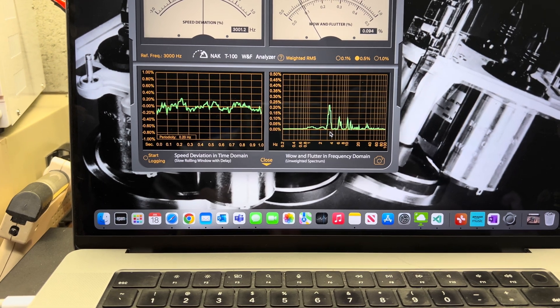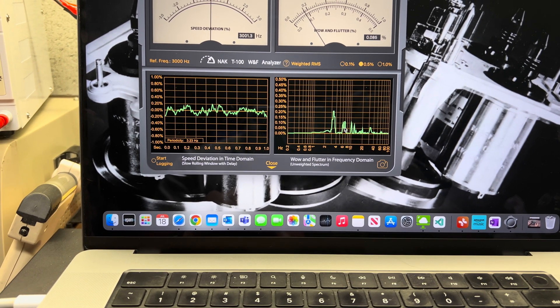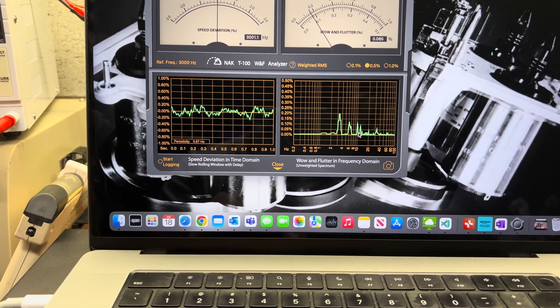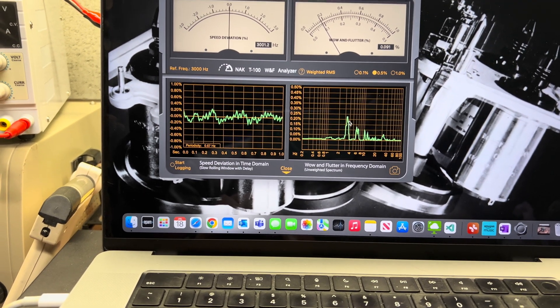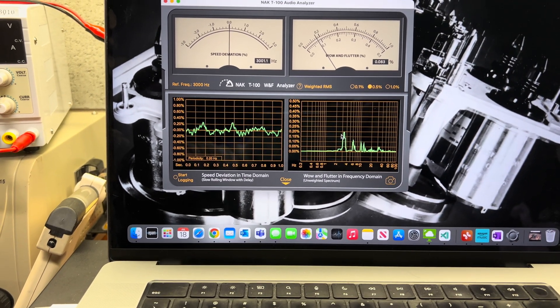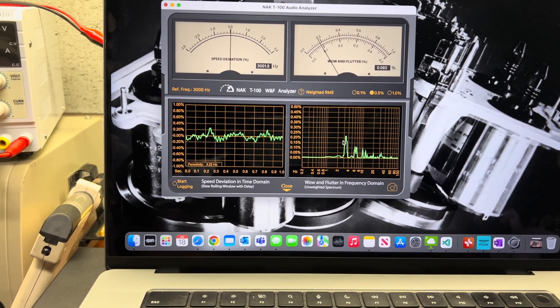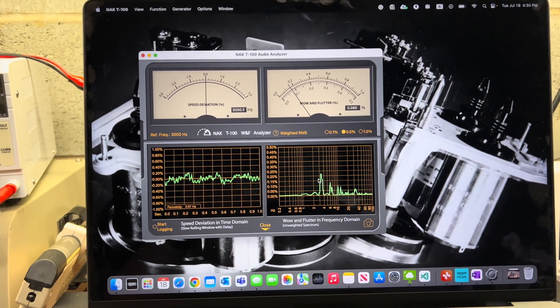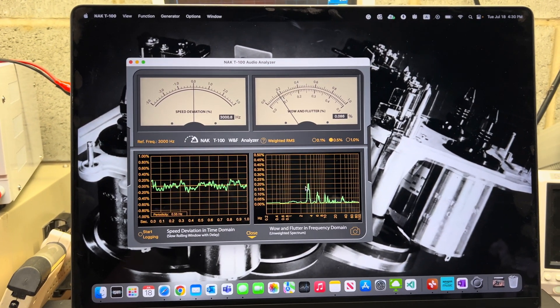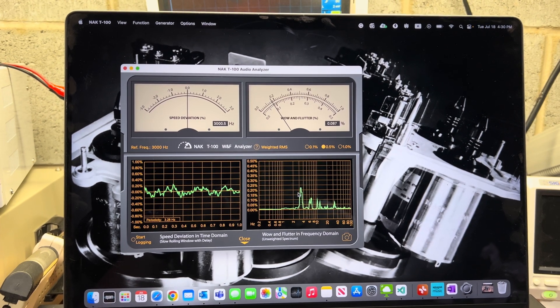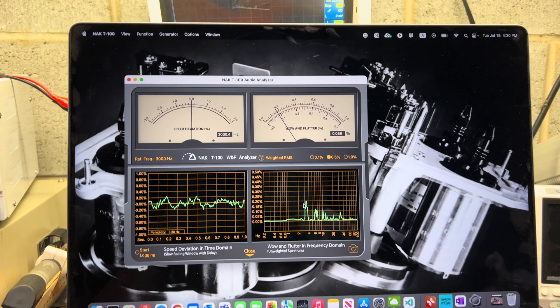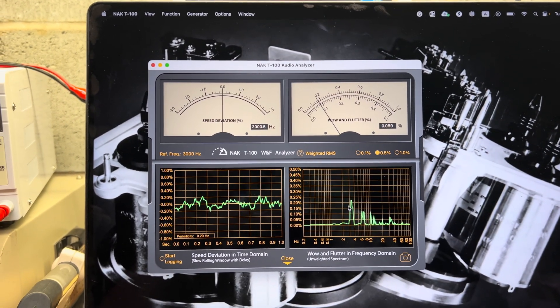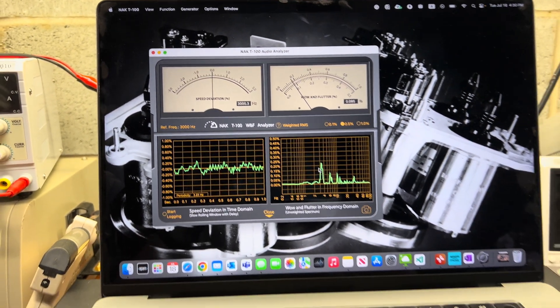spikes at 3.5 kilohertz, 7 kilohertz, and then 10.5 kilohertz, so 11 and so on. That's all connected to the belt and rotation of the capstan. That's the best belt I have, so probably if I can find a better belt it may go to 0.06 percent. So far not sure. And speed you see, ideal 3000 hertz, good.